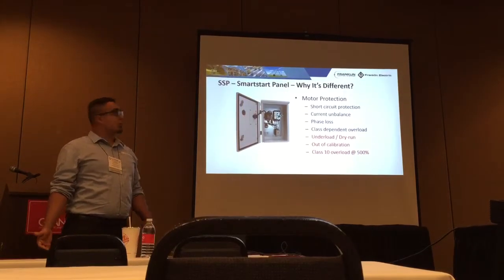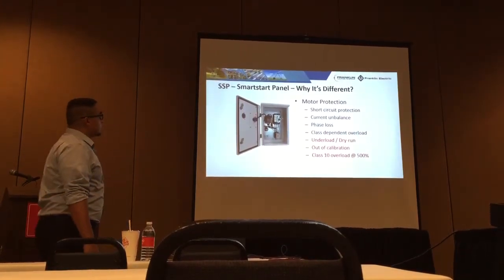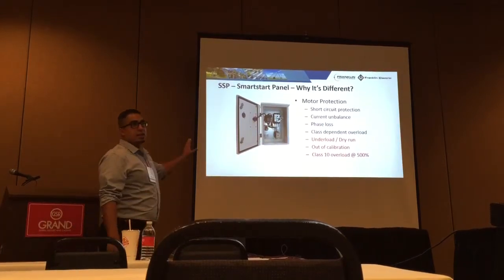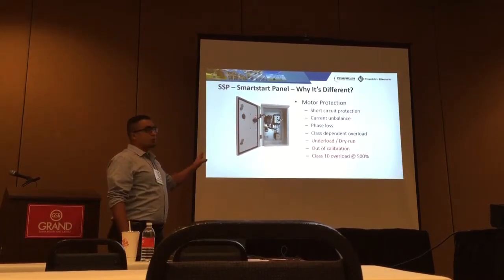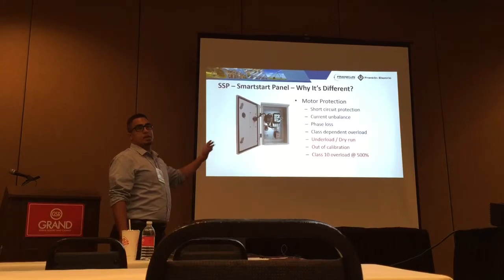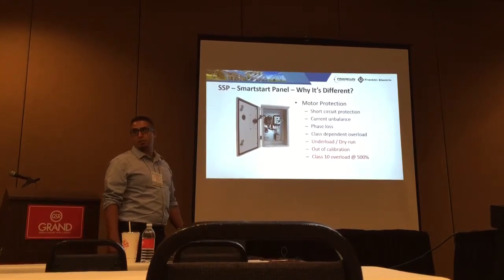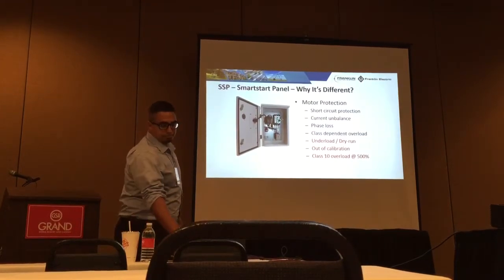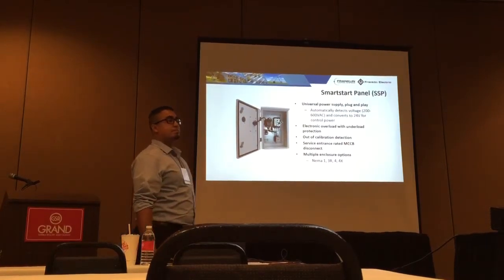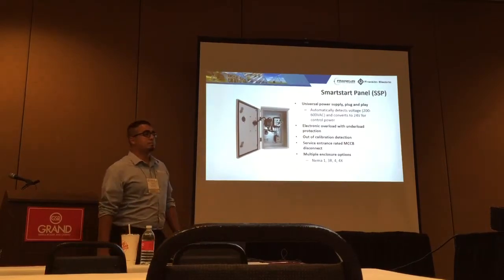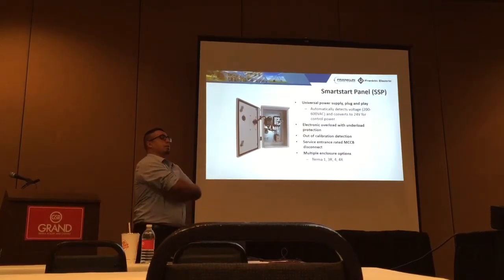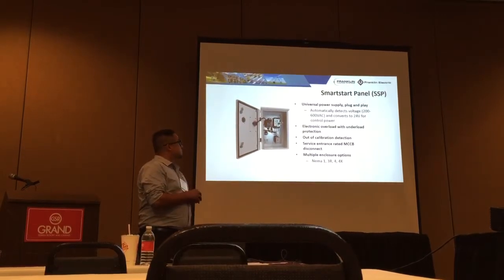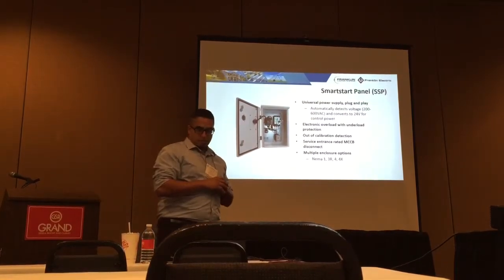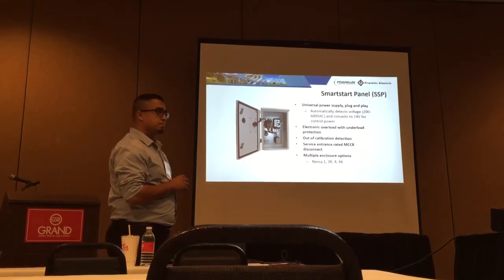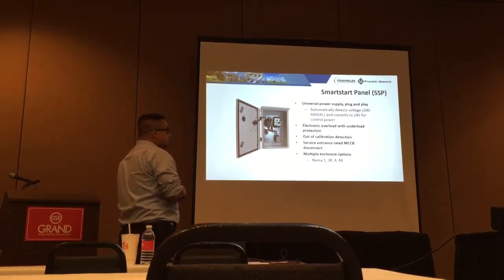Once you understand how the feature works, it's very easy to set. But this is out of the box. Nothing else has been added to this overload, but this has been engineered for Franklin submersible motors. I have a question. Yes. So when you first install that panel, how does it calibrate? When you first initially set the service factor amps on the Smart Start box? Mm-hmm. I'll get to that on the next slide.